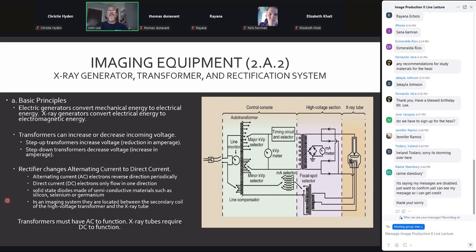Now, the rectifiers themselves are diodes that are utilized to correct the current for use in the X-ray tube. An X-ray tube only operates with direct current because electrons in an X-ray tube can only flow from cathode to anode. Thermionic emission only occurs at the cathode. Since we can't heat an anode up to cause thermionic emission, electrons don't flow back the other way. So to make the system more efficient, because we're using alternating current coming in off the wires into the building, into the generator, into the control panel, we have to at some point change that alternating current to direct current to be utilized by the X-ray tube. That's what the rectifiers are for.